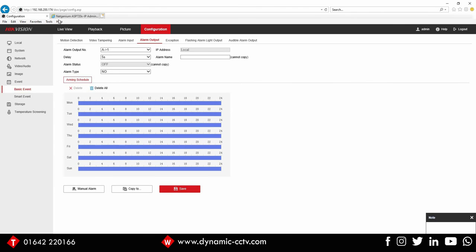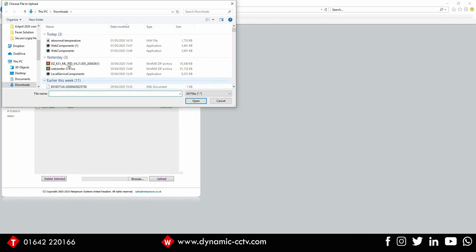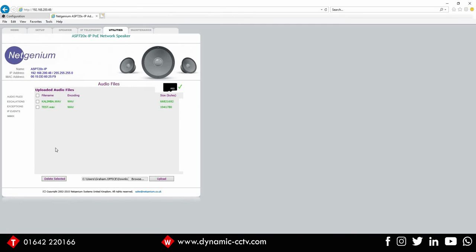And if I move across to our Netgenium speaker, I'm under the utilities tab at the moment. We can upload a message into the speaker. So I'm quickly going to do that now. Browse and upload the abnormal temperature message. It has to be a WAV file, so just make sure that you convert your audio file into a WAV before uploading it to the speaker. So that's our abnormal temperature message uploaded.